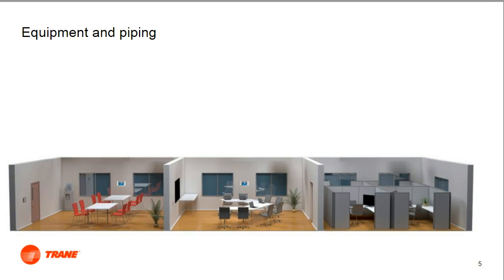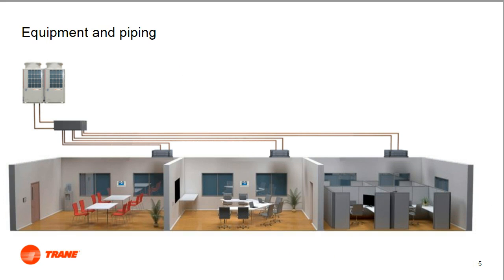There are typically three major subsystems that complete a VRF system, but there could be more. First, there's the VRF equipment and refrigerant piping. Here we are showing an air source VRF system. It is made up of the outdoor units. If the manufacturer uses a modular design, there will be more than one. The branch controller and the zone terminal units, often referred to as indoor units. And finally, the interconnected refrigerant piping. This VRF system recirculates air from the room and provides temperature control in the zones.